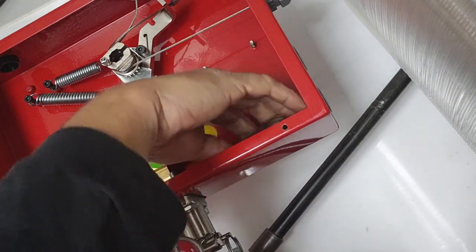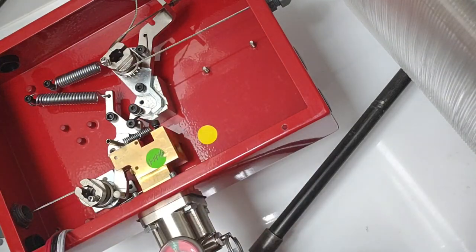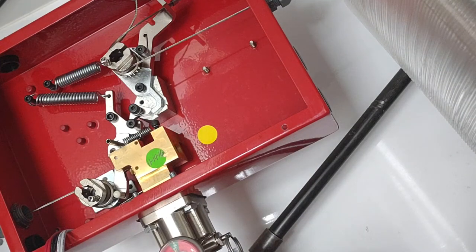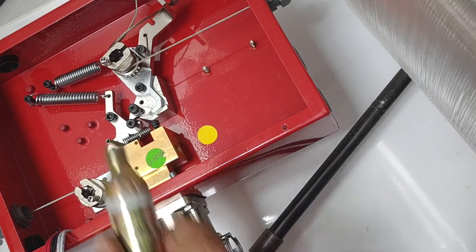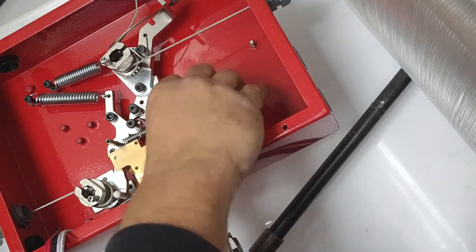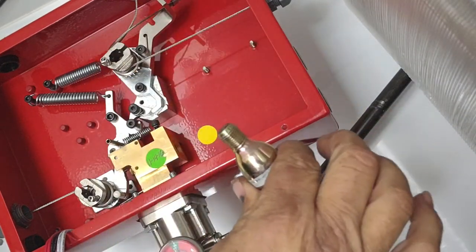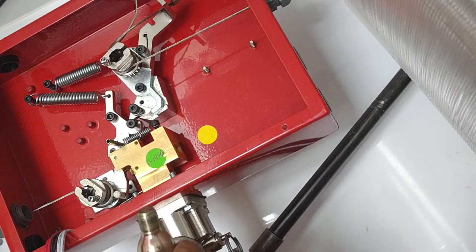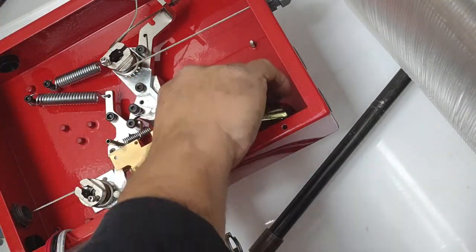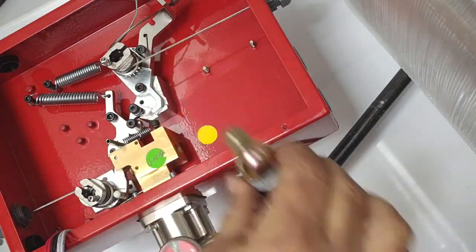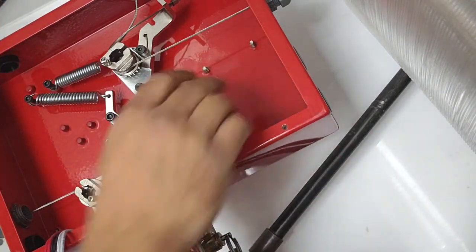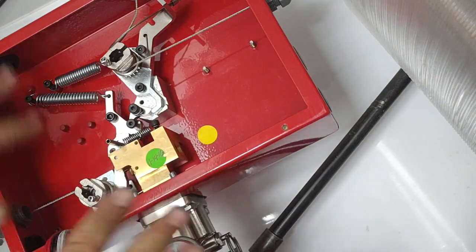Your system actually did actuate, but the cartridge wasn't in, so that saved you from dumping your system right there. I would suggest when you're traveling, open this up and take this cartridge out so that you don't risk hitting a bump and setting your system off. I'll set that to the side right there.